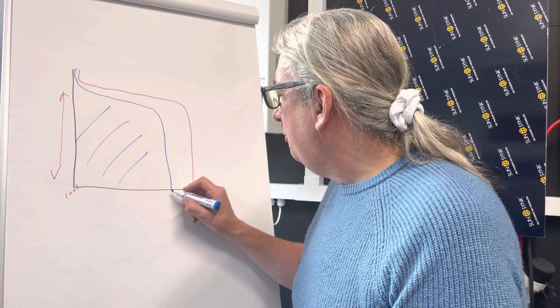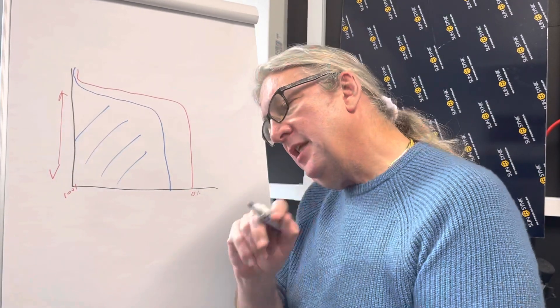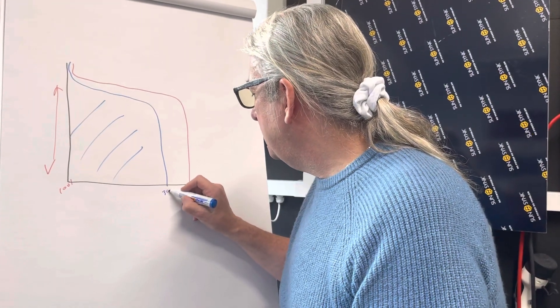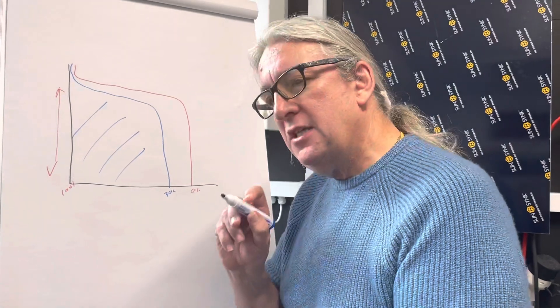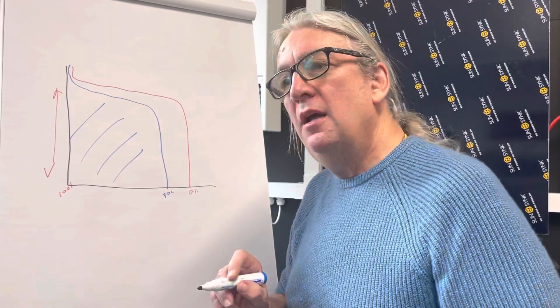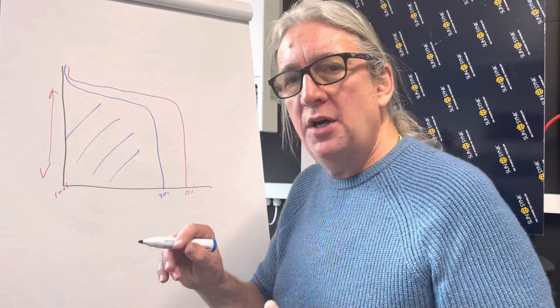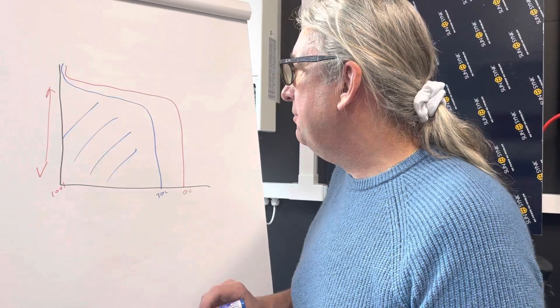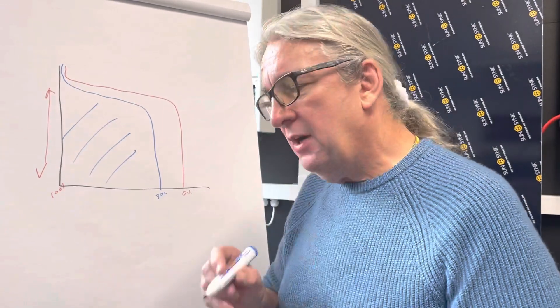The problem is, at this point here, this is my question: is the BMS still seeing, if this is 0, if this is the 30% line, is the BMS looking at the battery saying, oh, you've got 30% capacity, yet it hasn't got enough power to keep the DC bus bar going on the inverter? Because reality, the 30% is completely flat. And that's my question.